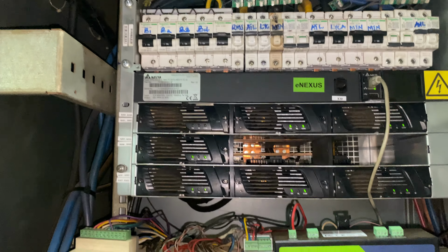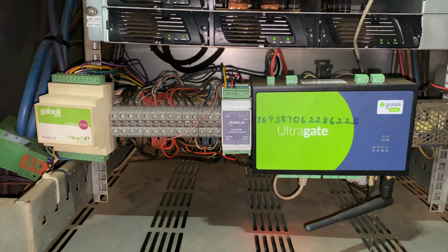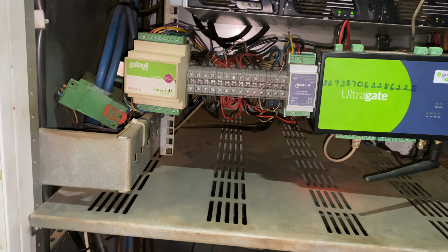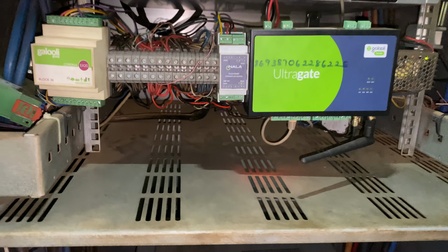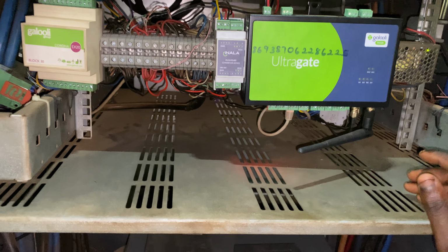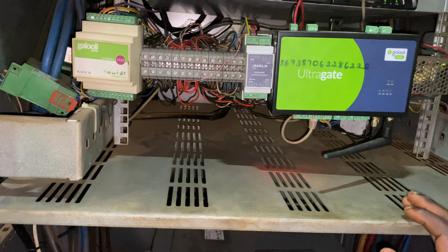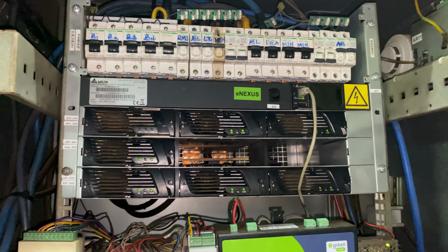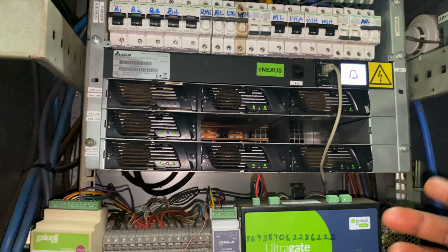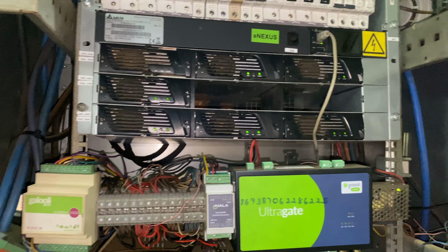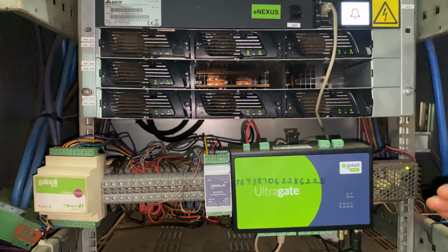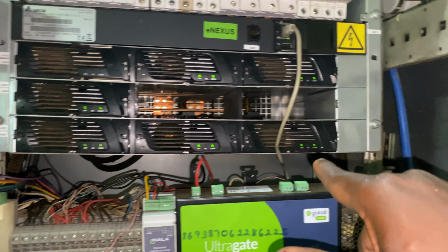The black wire which we are seeing behind is what we call the RTN. RTN stands for return wires, or the returning side, and it always carries 0 voltage. So the blue one carries the negative 48 voltage from the rectifier cabinet, and the black wire carries the 0 voltage. It also has its own bus bar.